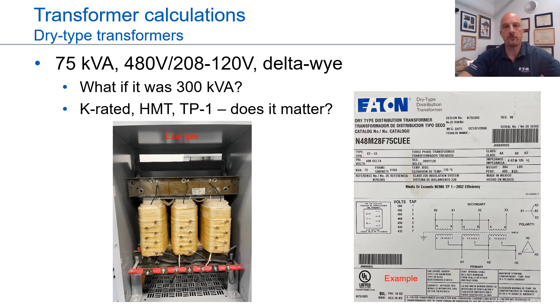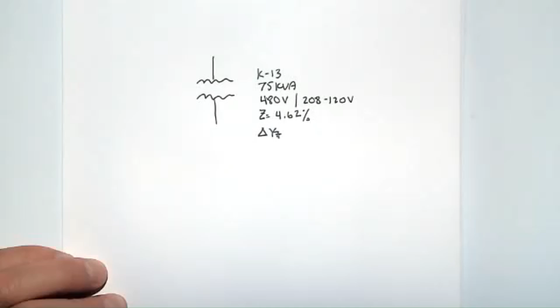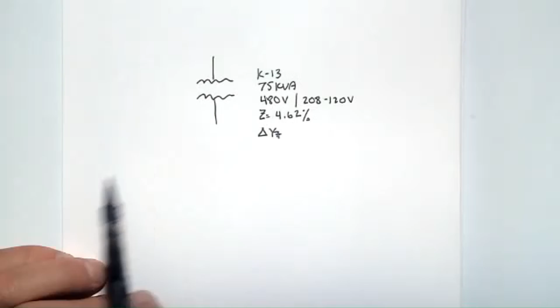Okay, so let's start in with the fun stuff with the actual transformers that we saw in the PQ lab here. This is one of my favorites, and you'll see why in a minute. It's 75 kVA, K13, which, by the way, K13, TP1, HMT, all kinds of strange transformer names might come up. That's not going to affect your calculations for these things. It actually does affect the impedance of the transformer when it's put together. But in fact, whatever's on the nameplate is what you need. So this information on the nameplate is all you need.